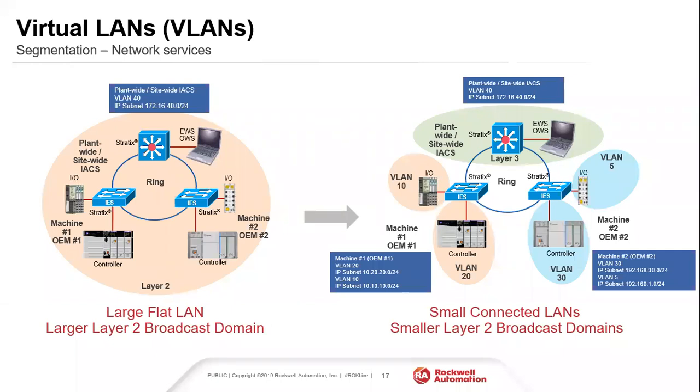Yeah, when we look at the topology, ring is an option, redundant star is an option, and I've got a couple of slides that will talk about the different options there. But all that ends up happening is the total number of ports that you put on the switch. You can put them either single VLANs or multiple VLANs, and all that's doing is just segregating the traffic so that it doesn't collide with each other. And what you do with the network after that, whether it's a fiber connection or a copper connection, it doesn't matter as long as it's coming out of those specific ports.